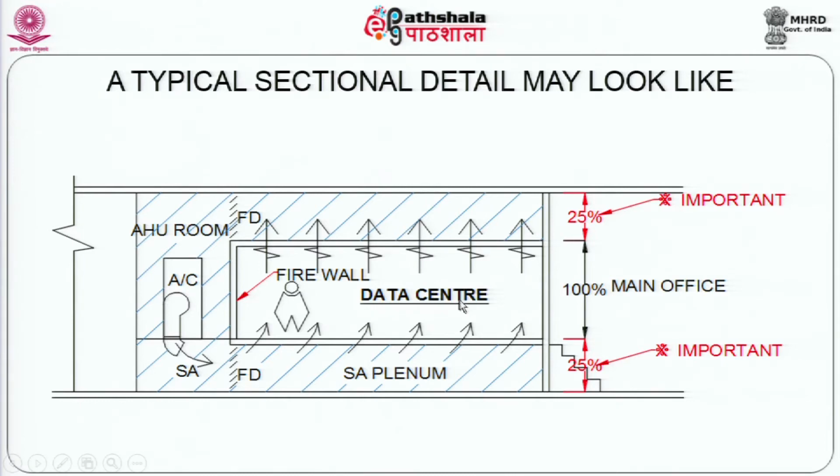So, the interface between the two has happened to the extent that today most data center equipment gets housed in racks. These racks are approximately about 0.9 by 0.9 meters. They look like huge cupboards which are about 2.1 to 2.2 meters in height and have a footprint of 0.9 meter by 0.9 meter. The front and the back are both openable and perforated for air movement and providing access. So, in other words, you are looking at a data center which will house equipment in racks with front and back openable, and these racks could be placed anywhere.